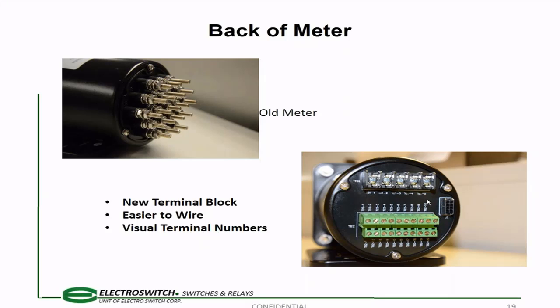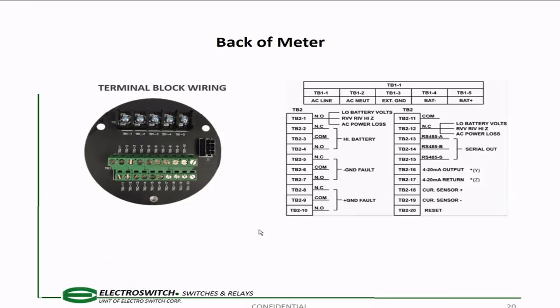So if you had a panel mount, which would be nice to have, you could actually tie in separate LEDs. If somebody had a panel they wanted to add the LEDs to, they just tie in the J1 output. So once again, it's just showing you which normally open, normally closed contacts. All your K1s are Form C, and then you can see where the 4 to 20 milliamp outputs and 4 to 20 milliamp returns are. This is the positive and negative for your current sensor. So it's actually fairly clear as far as how to hook this up.